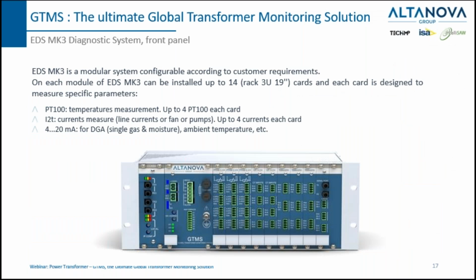In this slide, you can see the front panel of the EDS, our expert system for transformer parameters and for tan delta. You can see here different slots, different cards. Each card can be configured according to the application requirements. You can see here some examples for PT100, PT1000 for temperature measurements, or current measurement for line currents for fan, for example, or pumps, and for I²T calculation, or other kinds of analog or digital input. We have also a section dedicated to communication, and you can see here at the beginning, the first slot. We have in this case 2 fiber optic that can be used for a ring configuration up to the server, and some other accessories.